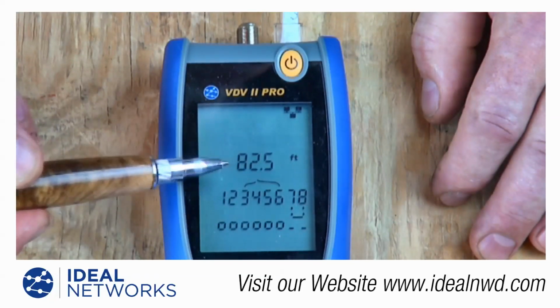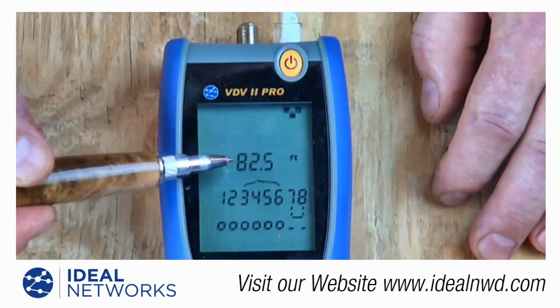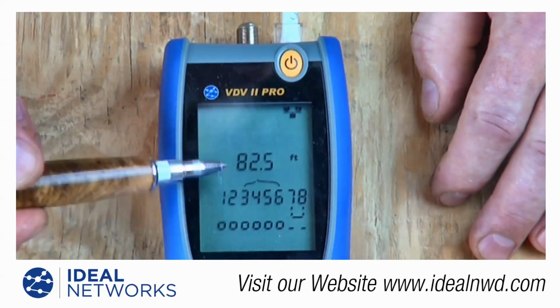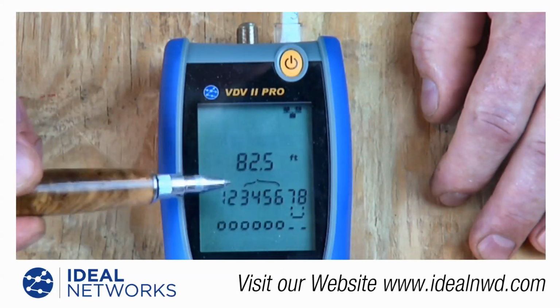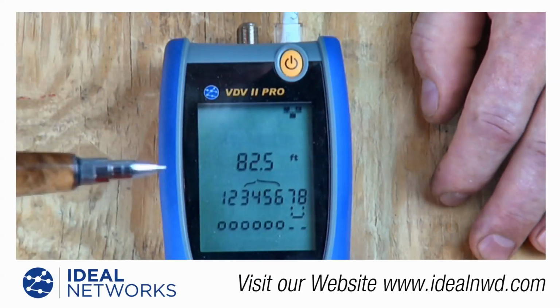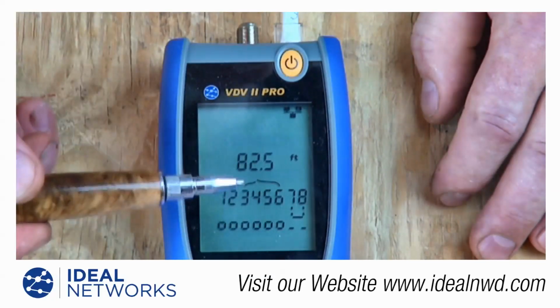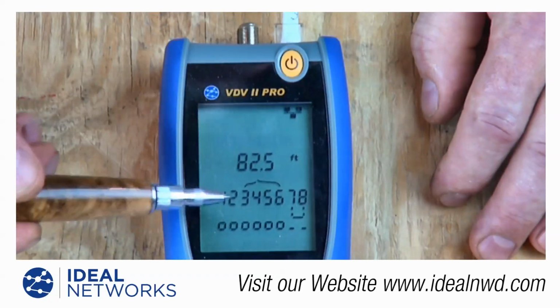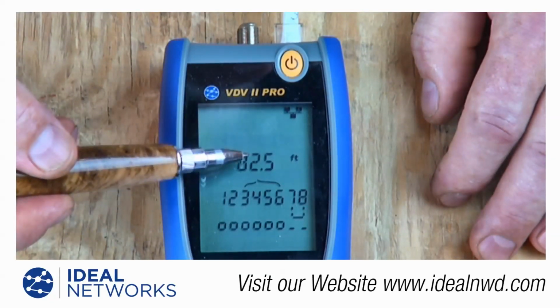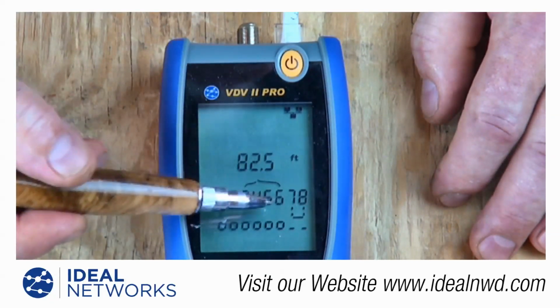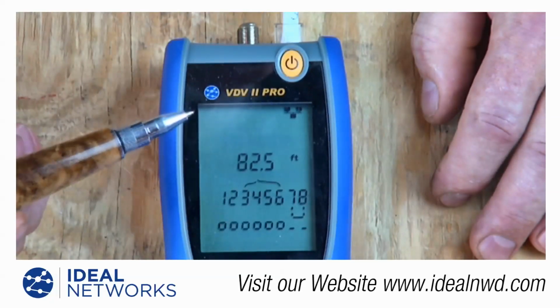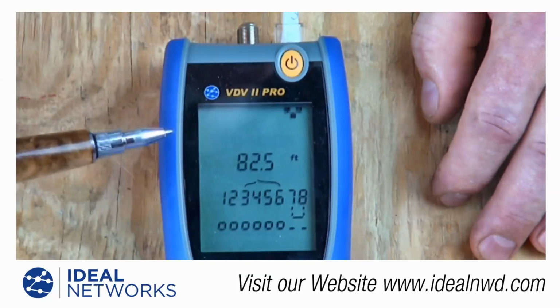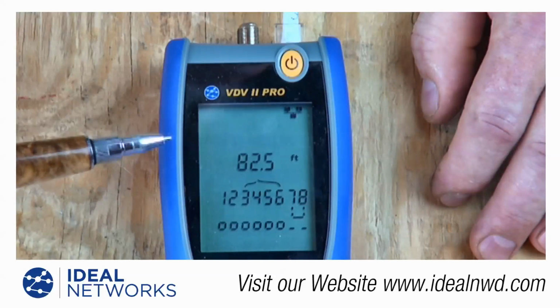So what I did was I actually put a cut in this cable about 20 feet back from the end of the cable. So this tester, again, is giving me the indication of distances to an open and distances to a short. So the opens we see are, one is the cut I made, and the other is the other two ends of the cable itself, and then there's the short there too. So very nice feature with the TDR function, and can be very useful when out there troubleshooting cables.